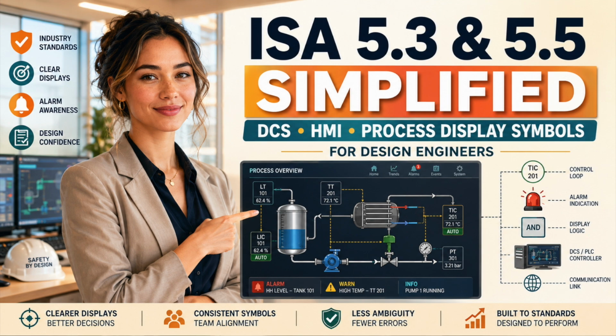A shared display, a shared controller, a computer function, an internal calculation, and a logic function do not communicate the same thing. Modern control systems execute many functions in software. One processor may regulate hundreds of loops, run sequences, calculate derived values, and generate alarms. One operator station may display thousands of variables. Drawing every function as a dedicated physical instrument creates a false architecture. Drawing the entire control system as one box destroys functional understanding.